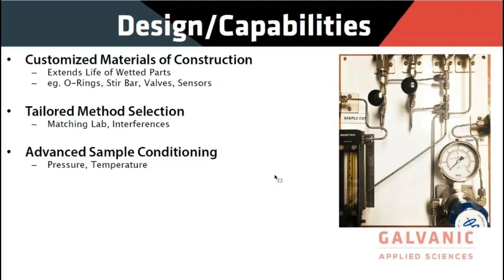At the same time, each method of analysis is tailored to the specific application. We look at making sure that we're matching the lab, if there's also a measurement performed there, and we look at any interferences that could be possible in the sample. For example, for an ammonia measurement, the first question we ask is, are you using an ISE or colorimetric method in the lab? And then if they're doing colorimetric, we dig deeper. Is it the Nessler method? Is it the salicylate method? And we make sure that there's no interferences in the sample. We can also do sample conditioning, so if we need to regulate the pressure or the temperature, and in some cases we can do filtration as well.